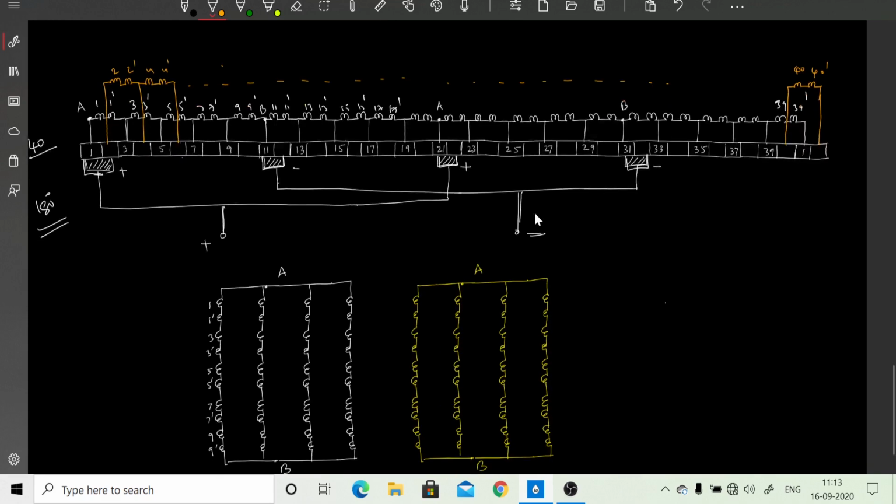Okay, so they are independent, they are closed, and they are symmetric. And they have an equal number of coils in each winding. Now one more important concept in duplex winding is that the brush we place on the commutator will now occupy a surface which comes in contact with 1 and 2. It will always be shorting, or connecting, 2 segments at a time.